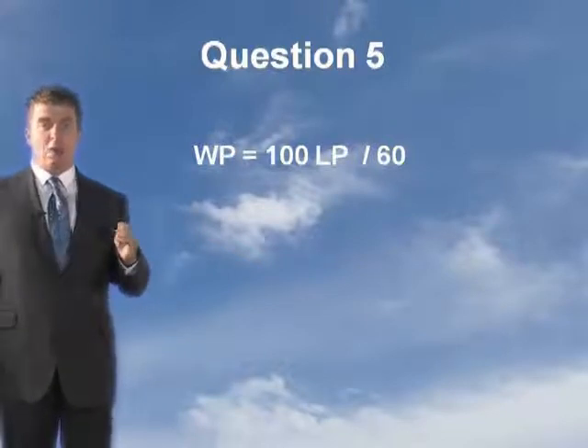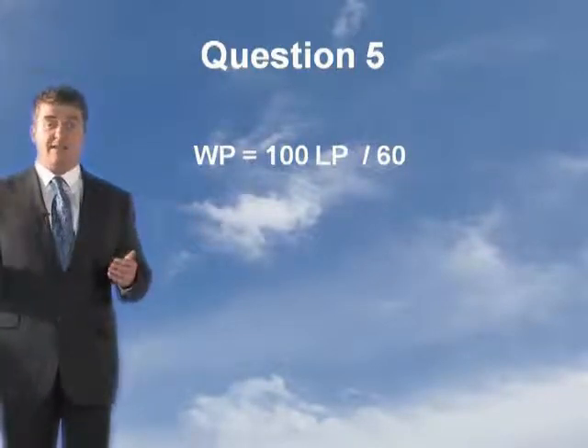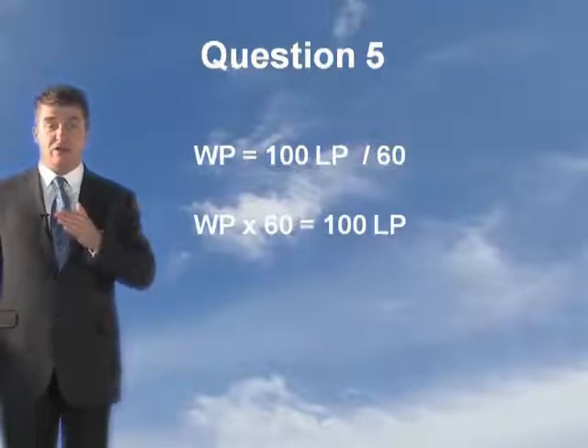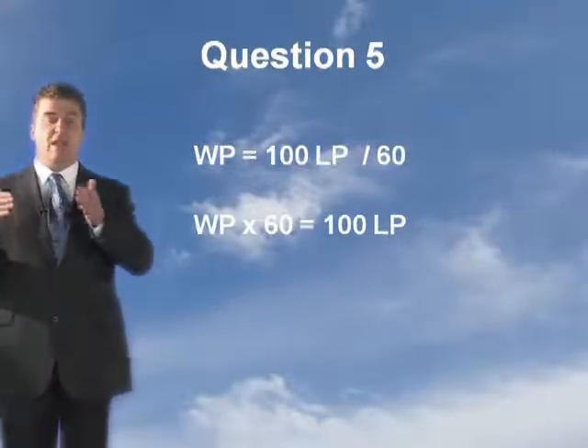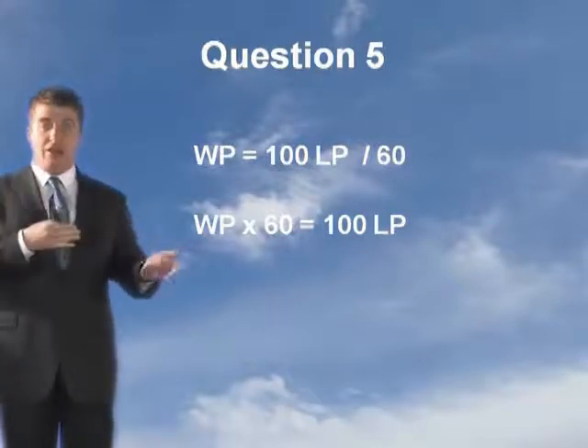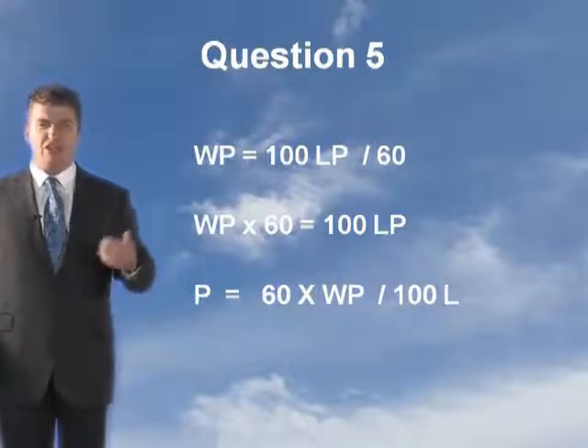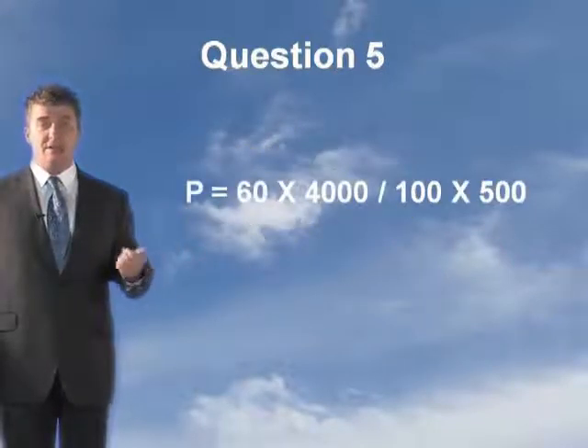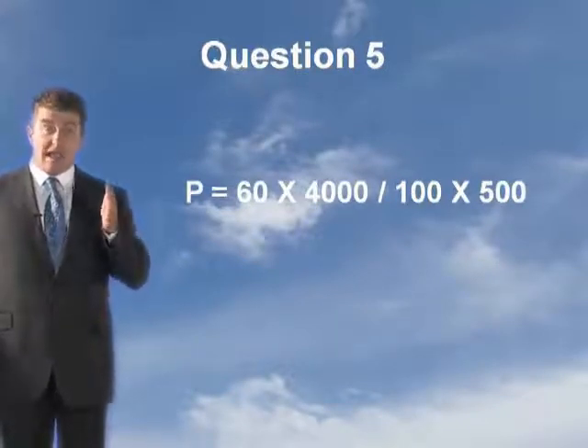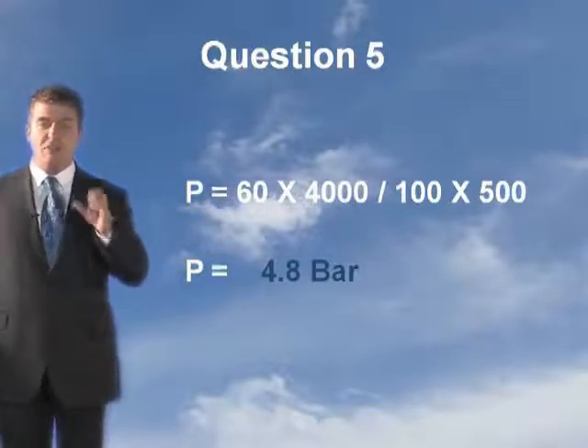To transpose it, you need to get everything attached to P to the other side. The whole right-hand side is divided by 60, so multiply both sides by 60: WP times 60 equals 100 LP. Then divide both sides by 100L, giving P equals 60 times WP divided by 100 times L. Putting the numbers in: P equals 60 times 4000 — don't forget it's in watts — divided by 100 times 500. P comes out at 4.8 bar. So you've got the pressure at the outlet.